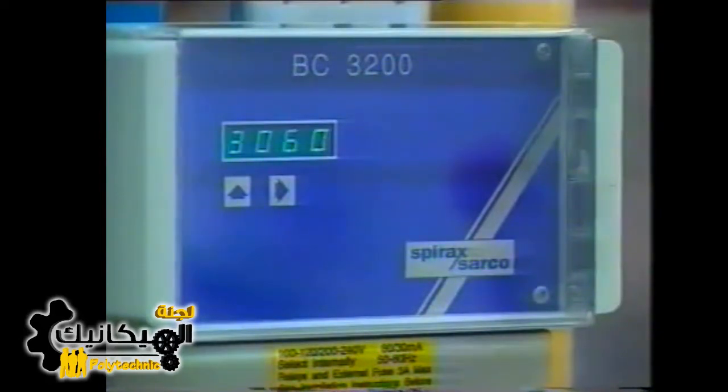What's not so apparent is that the actual boiling water level as measured by a level probe is not where you'd expect it to be. It is in fact much lower because the layer of foaming bubbles is substantially thicker than with normal TDS. This reduces the effective steam room within the boiler and leaves it vulnerable to carryover, even when the underlying water level is within normal operating limits. This is particularly so when the water rises to a high level, such as the top of the feed pump cycle or in response to an increase in demand. Fortunately, these problems can easily be avoided by using an appropriate means of TDS control.